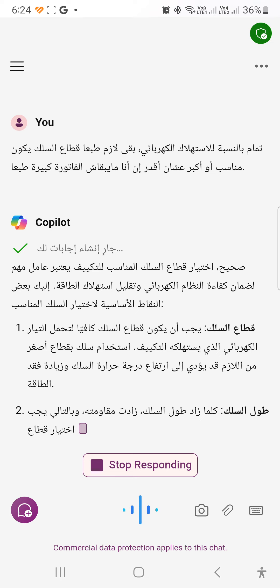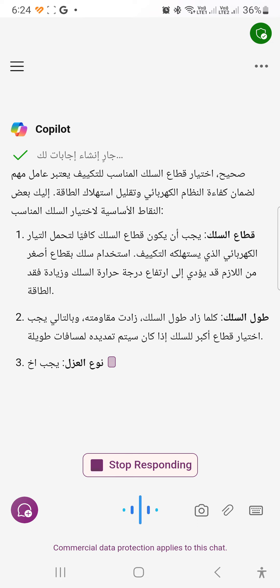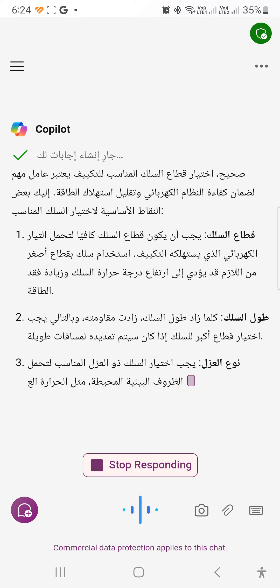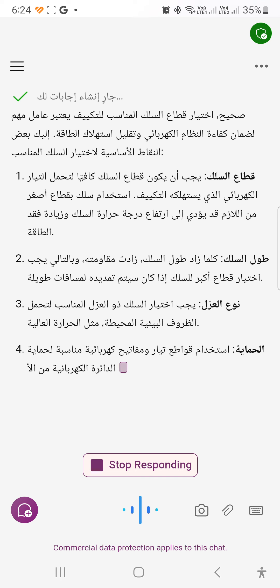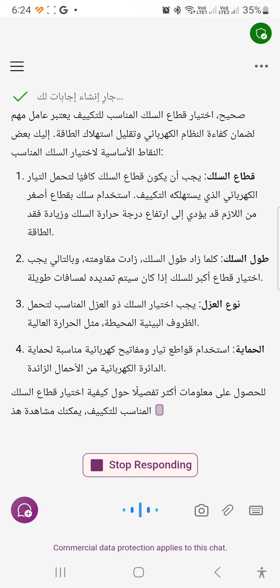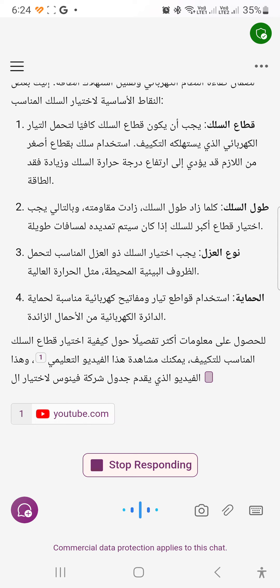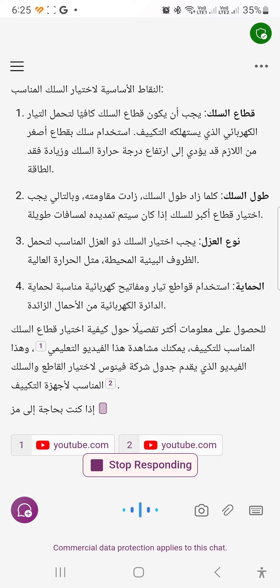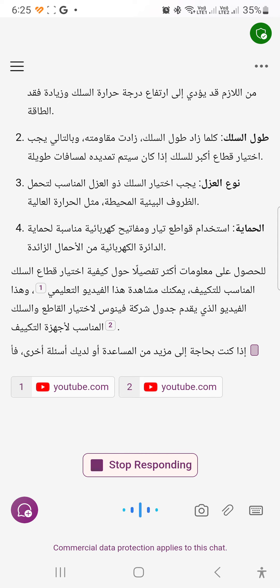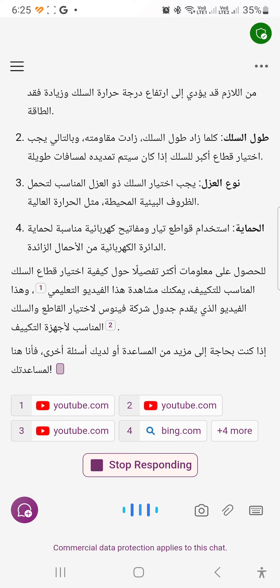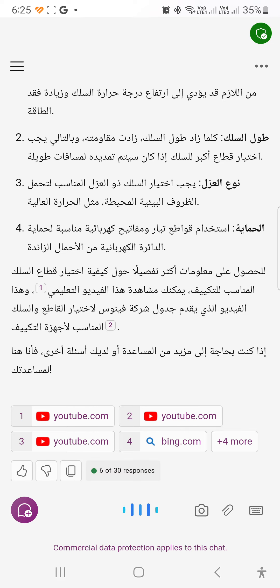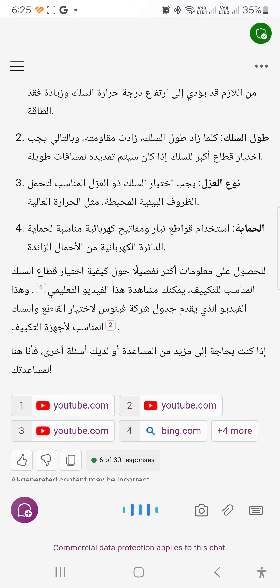يجب أن يكون قطاع السلك كافياً لتحمل التيار الكهربائي الذي يستهلكه التكييف. استخدام سلك بقطاع أصغر من اللازم قد يؤدي إلى ارتفاع درجة حرارة السلك وزيادة فقد الطاقة. كلما زاد طول السلك زادت مقاومته، وبالتالي يجب اختيار قطاع أكبر إذا كان سيتم تمديده لمسافات طويلة. يجب اختيار السلك ذو العزل المناسب لتحمل الظروف البيئية مثل الحرارة العالية. كما يجب استخدام قواطع ومفاتيح كهربائية مناسبة لحماية الدائرة من الأحمال الزائدة. يمكنك مشاهدة الفيديو التعليمي وجدول شركة فينوس لاختيار القاطع والسلك المناسب لأجهزة التكييف.